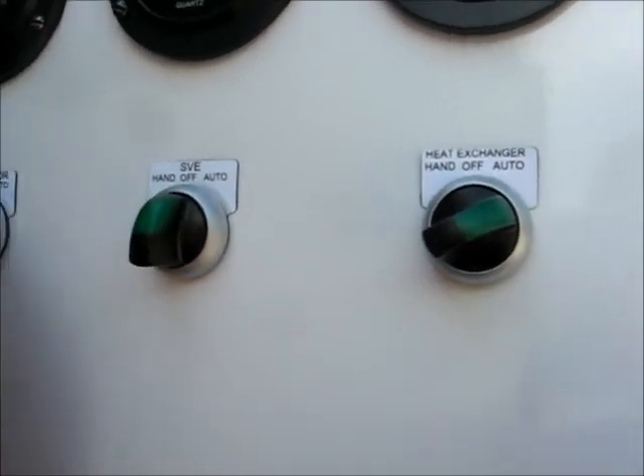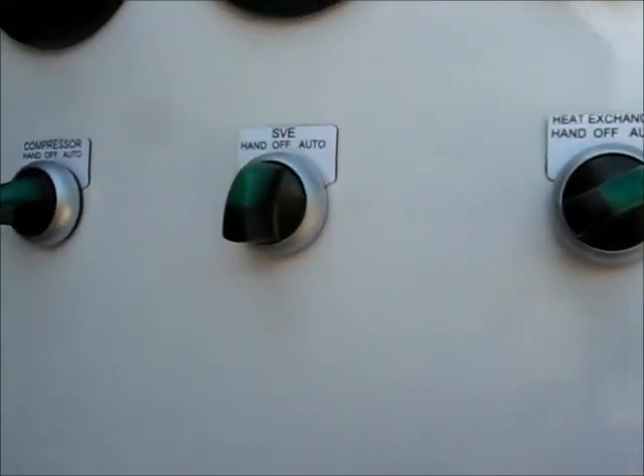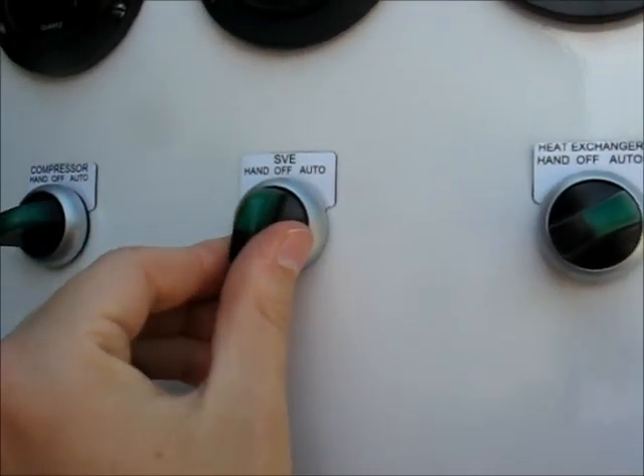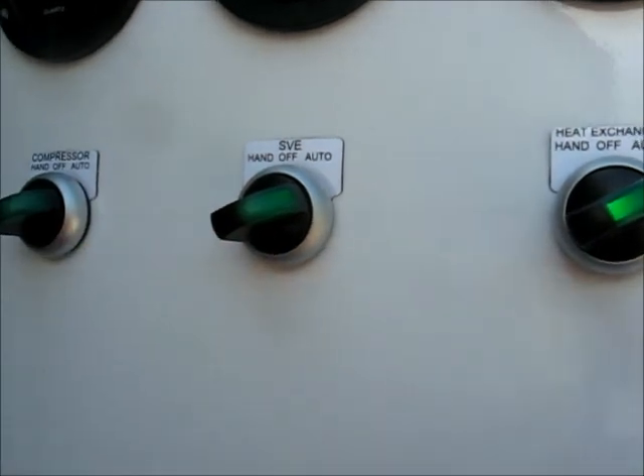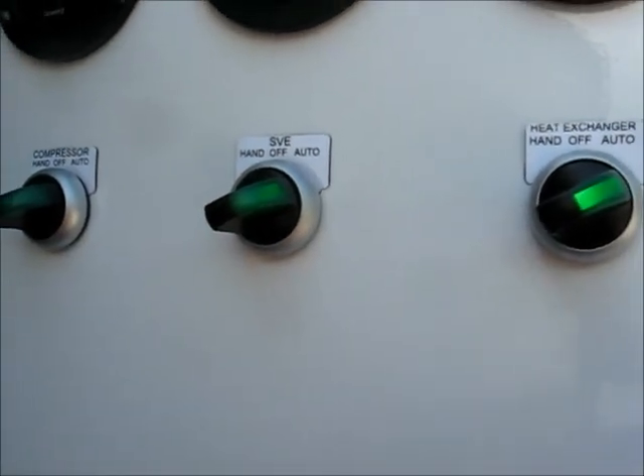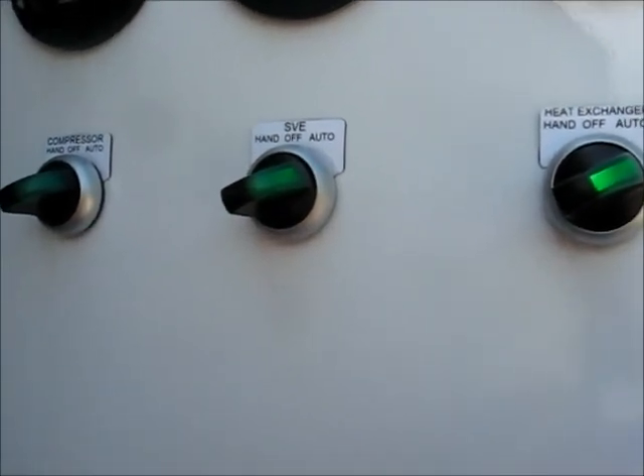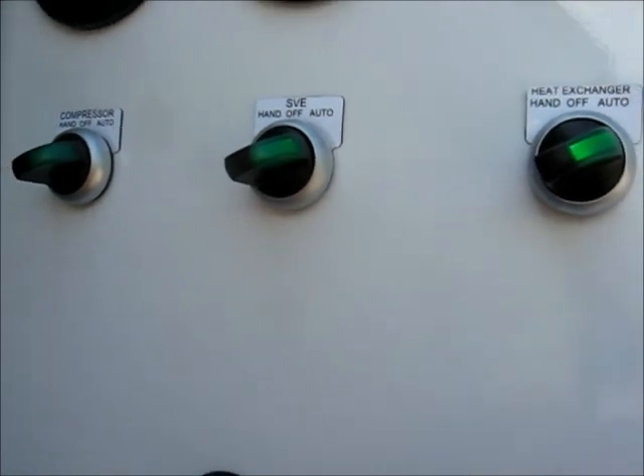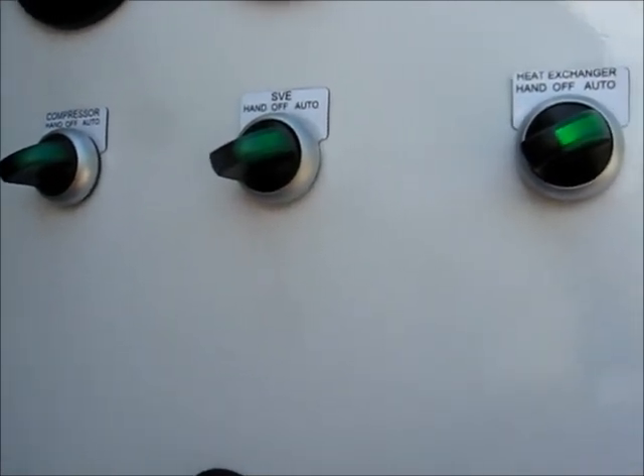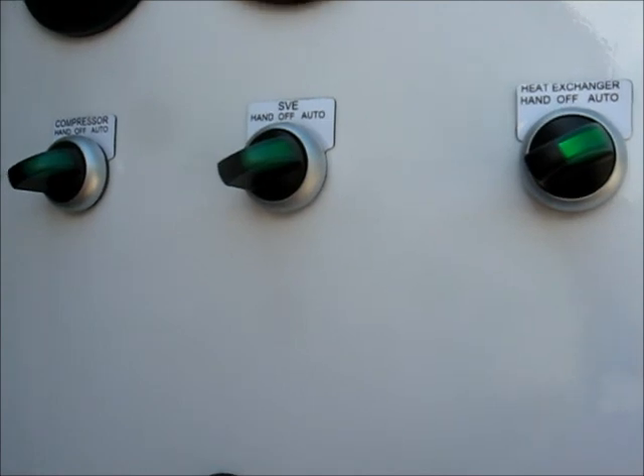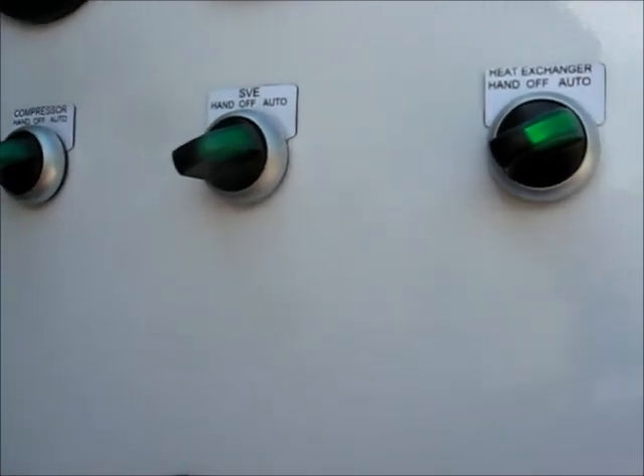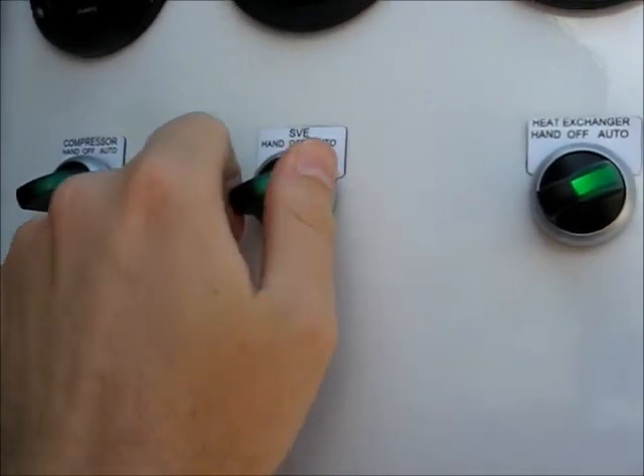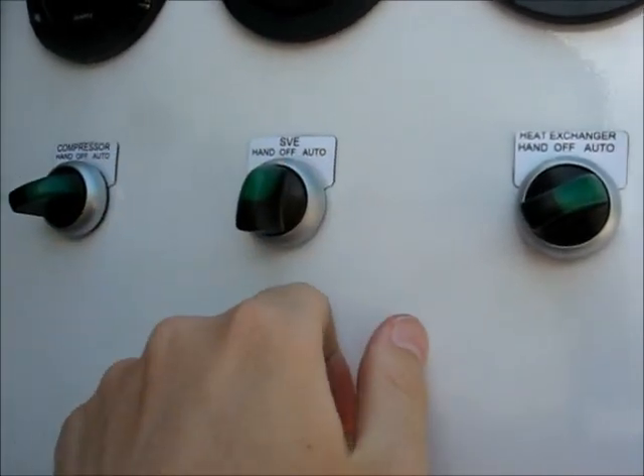So we'll turn that on. You can see the air compressor won't come on either. When we turn the SVE on, they should all come on. You can hear the SVE just cut on, the heat exchanger's on. Give it a couple of seconds, about 10 seconds or so, and we should have the air compressor kick on. There it is. You can hear it kick on. That's just to prevent too much inrush. So again, I'll shut the SVE off and everything should go off. And there it is.